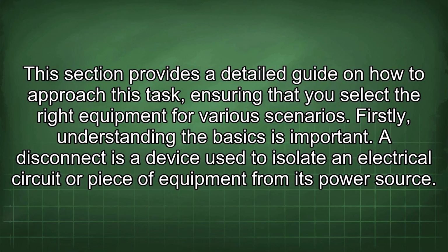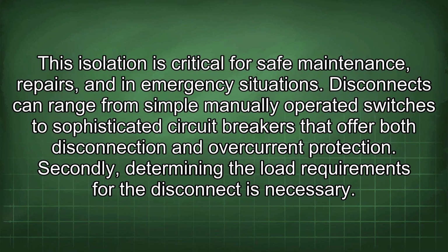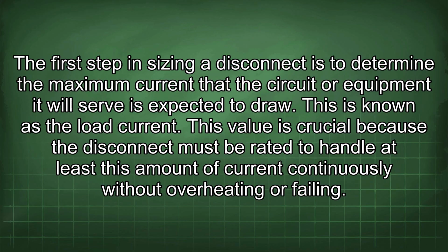A disconnect is a device used to isolate an electrical circuit or piece of equipment from its power source. This isolation is critical for safe maintenance, repairs, and in emergency situations. Disconnects can range from simple manually operated switches to sophisticated circuit breakers that offer both disconnection and overcurrent protection. Secondly, determining the load requirements for the disconnect is necessary. The first step in sizing a disconnect is to determine the maximum current that the circuit or equipment it will serve is expected to draw. This is known as the load current.